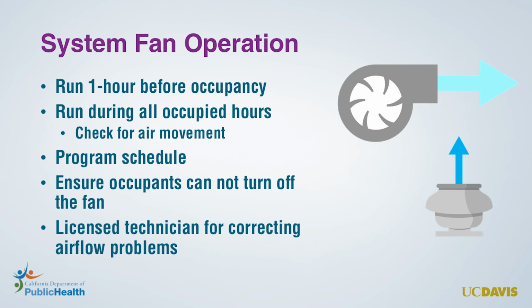Program the fan schedule in your thermostat or building automation system and make sure the occupants cannot turn off the fan. Some thermostats designed for homes do not allow programming a ventilation fan schedule. These types of thermostats should be replaced.